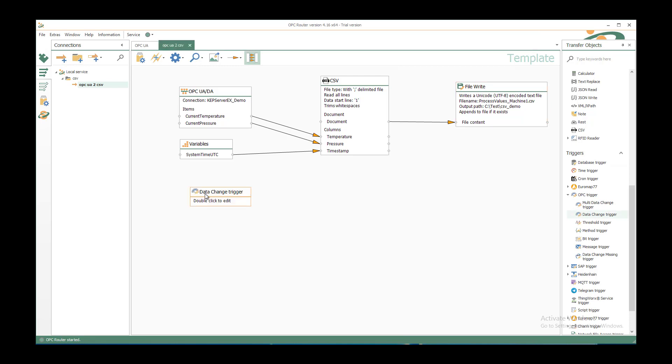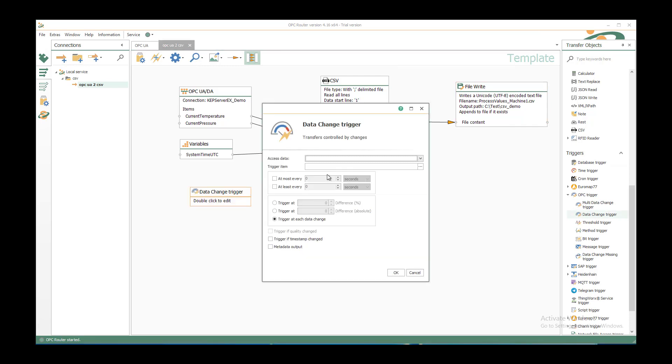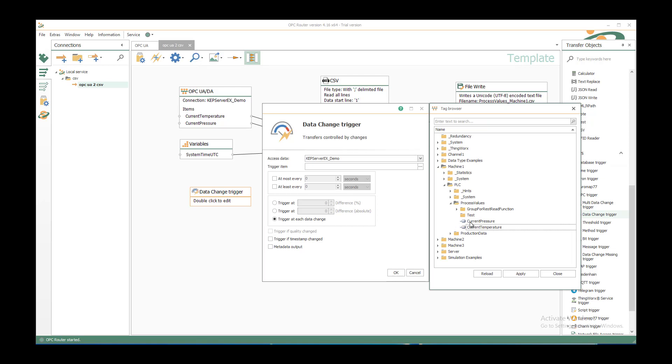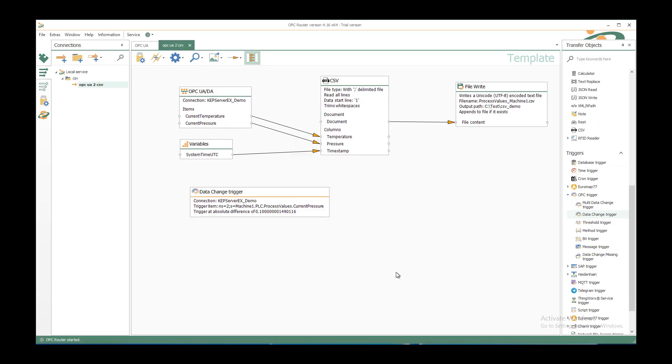And under OPC trigger we just use the data change trigger. Just double click to edit and we can say we want to select the KEPServer OPC server as before. And a trigger item we want to select the current pressure. Every time the current pressure changes about 0.1 difference, because it's a floating point. We don't use a trigger at each data change for this type normally. So we can say OK.